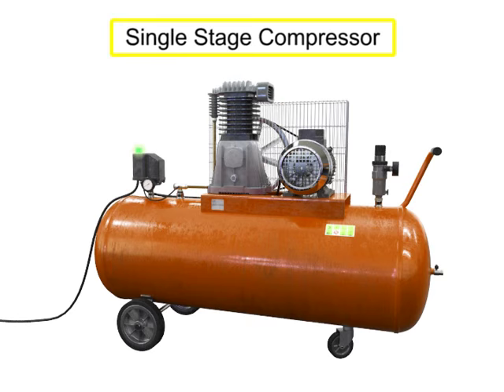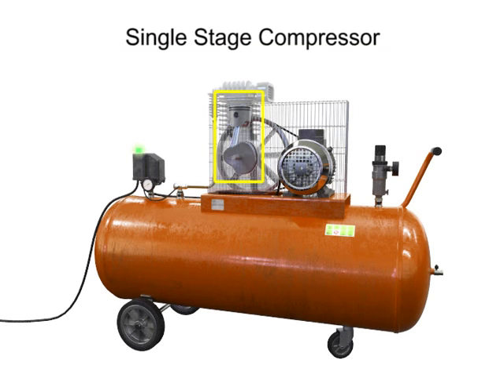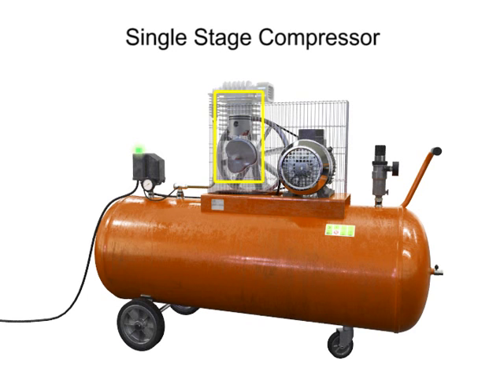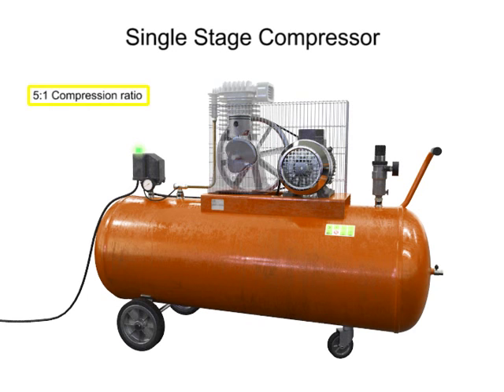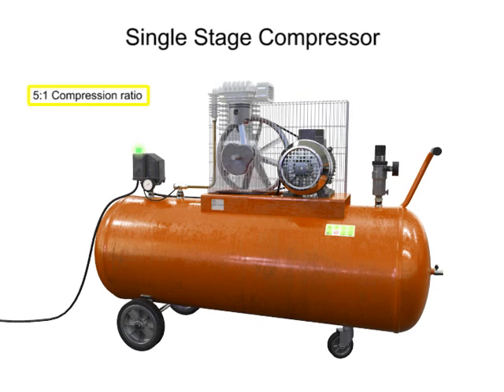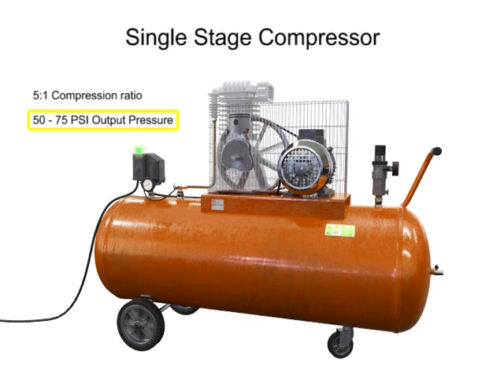This is a single stage compressor. It has only one piston and cylinder and compresses the air in only one stage. A single stage compressor typically has a compression ratio of 5 to 1, with an output pressure of about 50 to 75 psi.